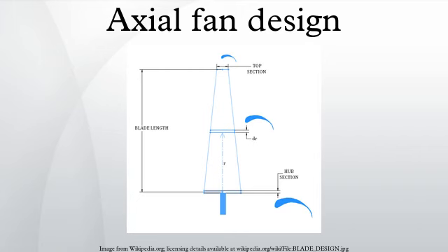Stalling effect: the cause of stall is the separation of the flow from the blade surfaces. This effect can be explained by the flow over an airfoil. When the angle of incidence increases at the entrance of the airfoil, the flow pattern changes and separation occurs. This is the first stage of stalling, and through this separation point the flow separates, leading to the formation of vortices and backflow in the separated region. For further explanation of stall, rotating stall, refer to compressor surge.